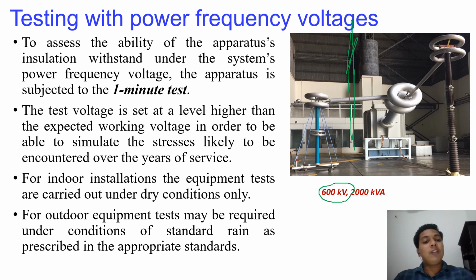To assess the ability of apparatus insulation to withstand the system's power frequency voltage, the apparatus is subjected to a 1 minute test. How much voltage do we apply? It will not be the normal power frequency voltage, it will be a bit higher. How much higher depends on the country where it will be used and what kind of stresses it undergoes. Based on that, we decide and apply this power frequency voltage.